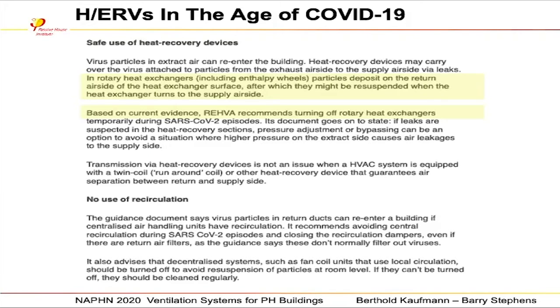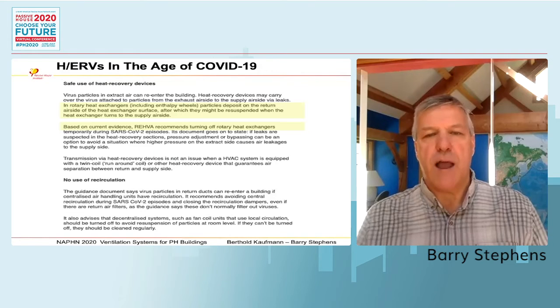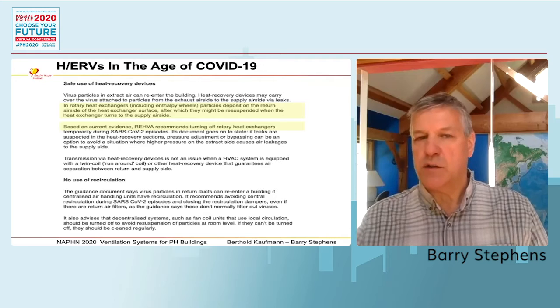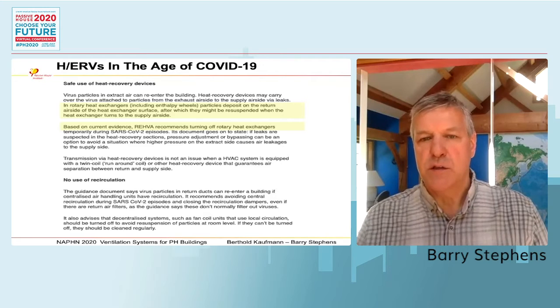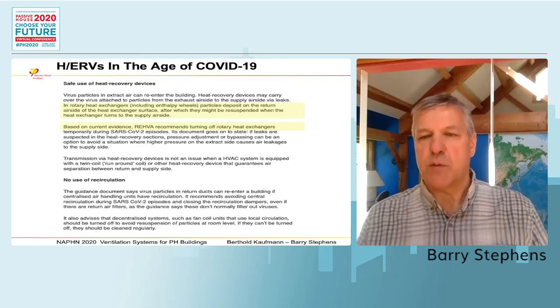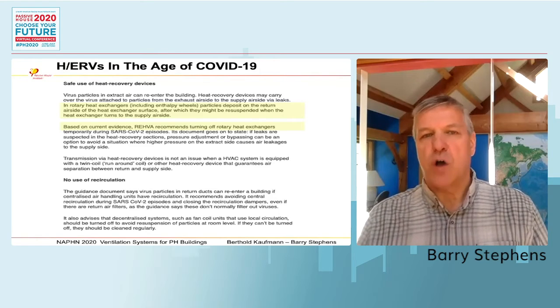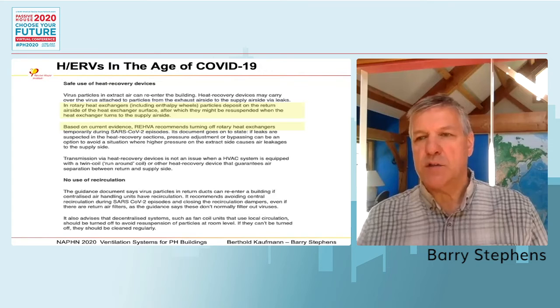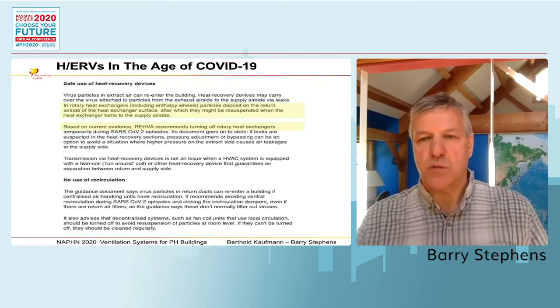The challenge is that viruses on an outgoing airstream adhere to that wheel in the same way that moisture would. That wheel then turns, and those viruses could be picked up by the incoming air and brought back into the building and actually distributed. So their guidance is that wheels should be turned off during these periods. And so that's something to keep in mind. Wheels don't have the cross-flow contamination limits that you can get with a counterflow heat exchanger that's well sealed.